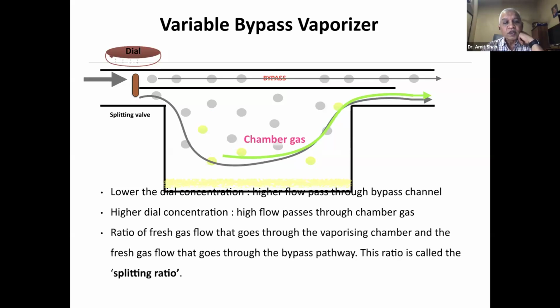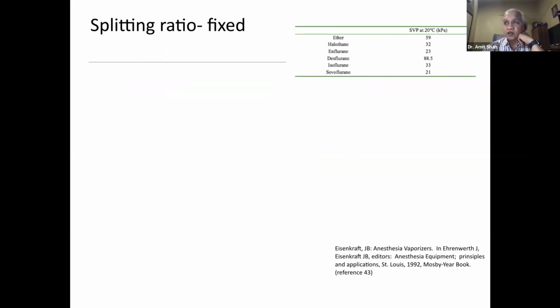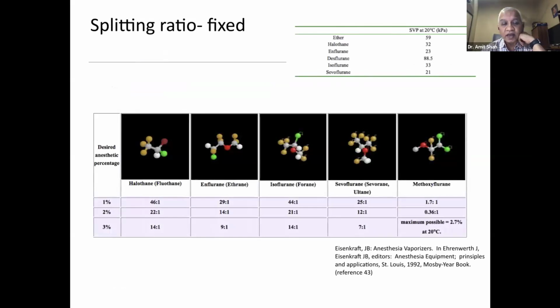This ratio of the gas flow that goes through the vaporizing chamber to the fresh gas flow that passes through the bypass pathway is called the splitting ratio. Okay, a very important terminology: splitting ratio. Now this splitting ratio is fixed, and it is based on the vapor pressure. It is specific to each particular agent, and it is based on two things: one, the saturated vapor pressure, and two, the end-tidal sevoflurane or isoflurane concentration which we want. So the vapor pressure might be the same for isoflurane and halothane, but the splitting ratio will be different because we want a different end-tidal concentration, since their MAC values are different. So it is based on their requirement.